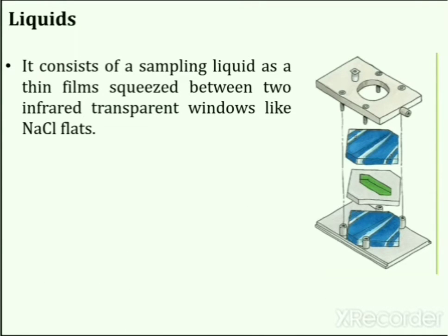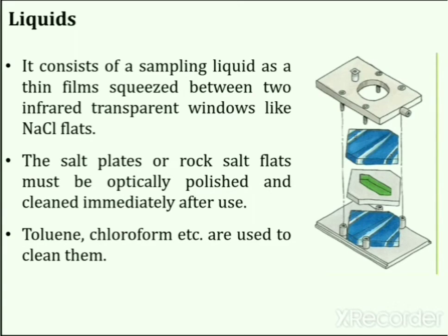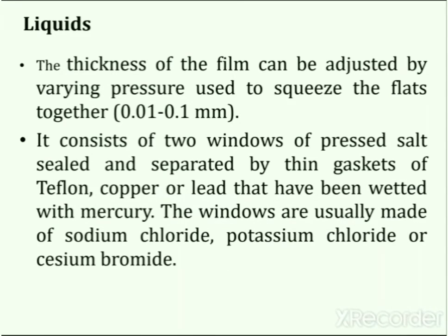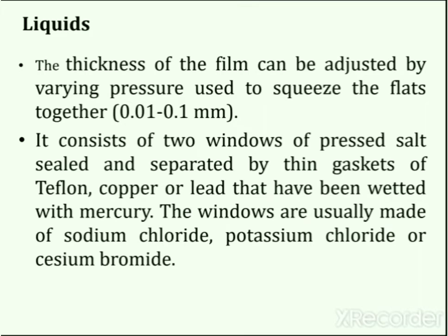Liquid samples are analyzed by making a thin film squeezed between two infrared-transparent windows like NaCl flats, also called salt plates or rock salts. The flats must be optically polished and cleaned using toluene, chloroform, etc., and should be dry, handled only by their edges. Thickness of the film can be adjusted by varying the pressure used to squeeze the flats together, and thickness can vary between 0.01 to 0.1 mm. The cell consists of two windows of pressed salt sealed and separated by thin gaskets of teflon, copper, or lead wetted with mercury. Windows are usually made of sodium chloride, potassium chloride, or cesium bromide. One cell contains the sample and a second contains the pure solvent placed in the reference beam, so that solvent absorptions are cancelled out and the spectrum recorded is that of the solute alone.